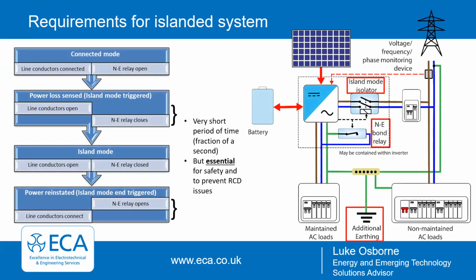You've got to have an island mode isolator, to ensure that if there is an outage, the battery or the inverter connected to it cannot export power back to the grid - because people could be working on the fault, rightly assuming that no power is going to be exported. There also needs to be a neutral earth bond relay, and these items are generally contained within the inverters. So it's critically important to understand what is being offered by these manufacturers.